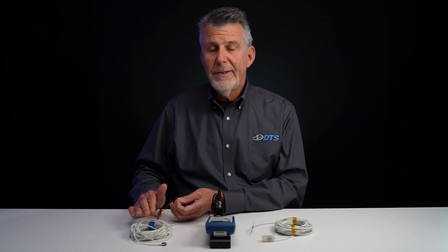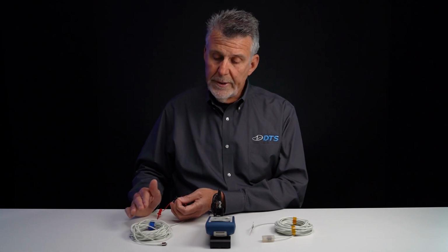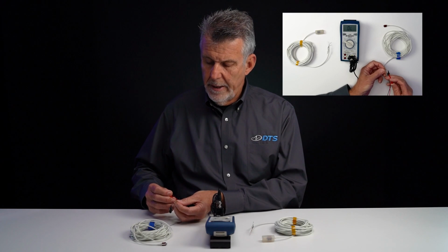Over here, I have a sensor that failed the diagnostics the last time I tried to use it. Specifically, it failed the offset check with a very large number that was out of tolerance, and it really miserably failed the shunt check. And so that made me think maybe there's something wrong with the sensor. But an easy way to verify that is to run these tests with the multimeter on the bench. I'm going to run the same checks that I did on the sensor that I know is functioning.